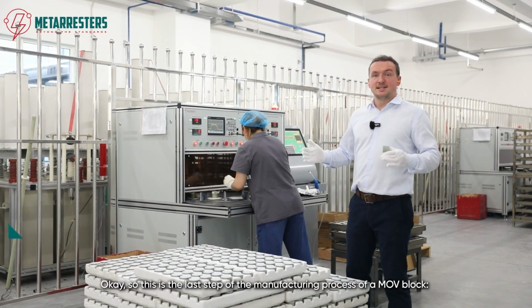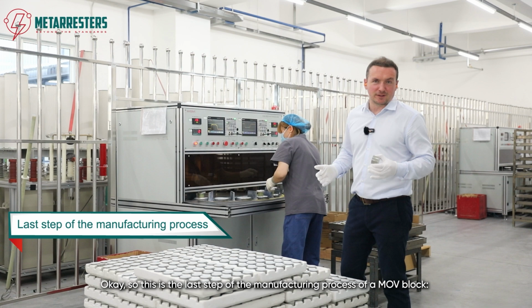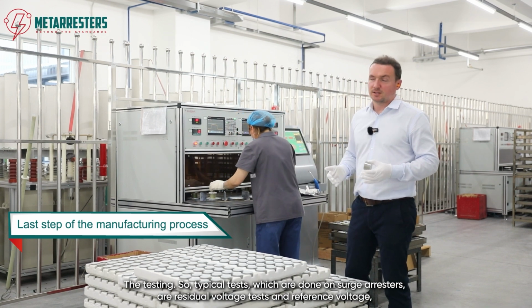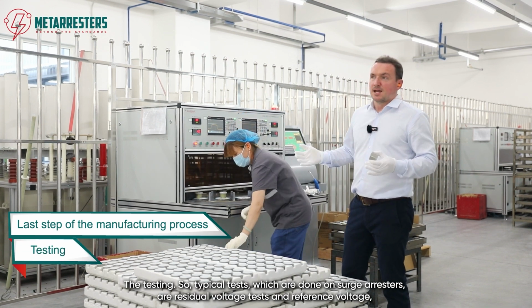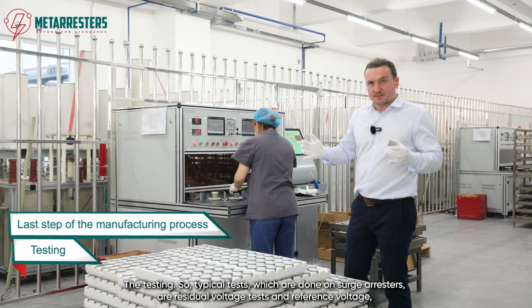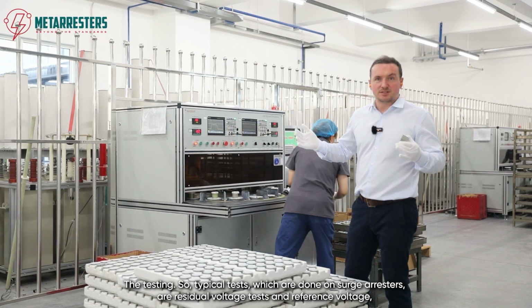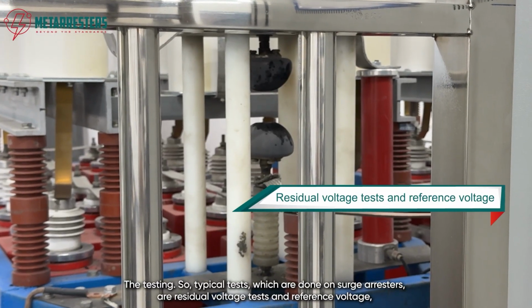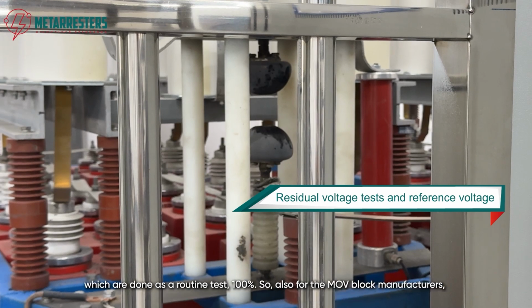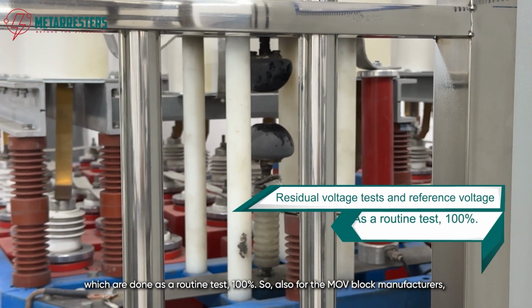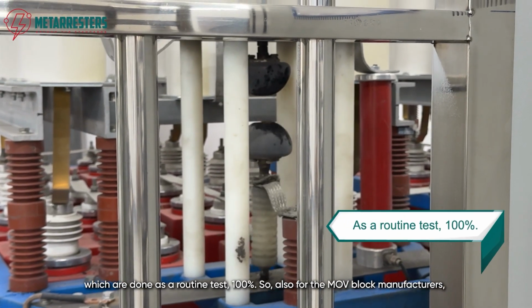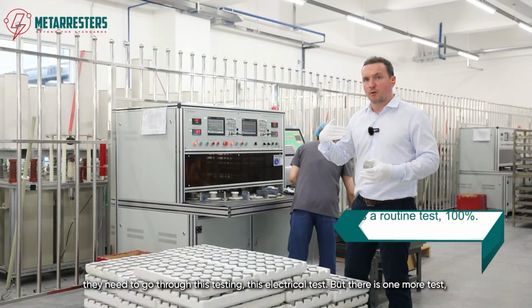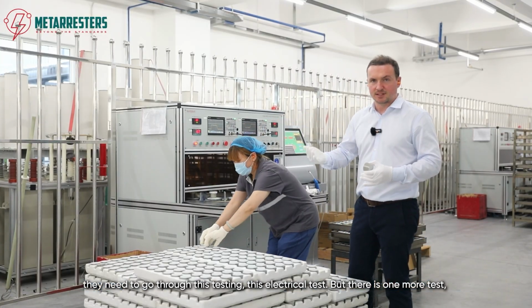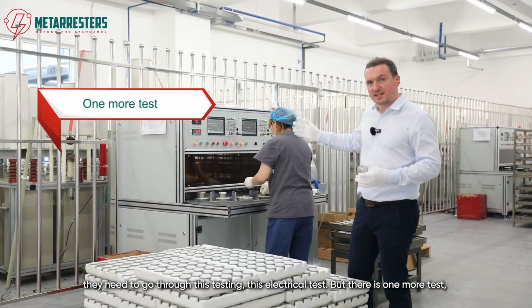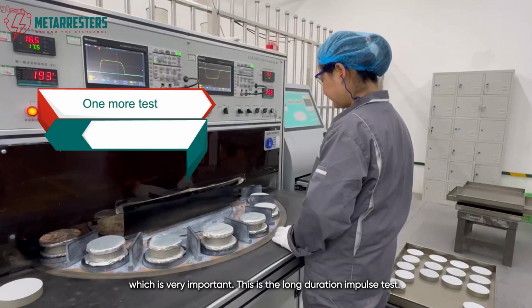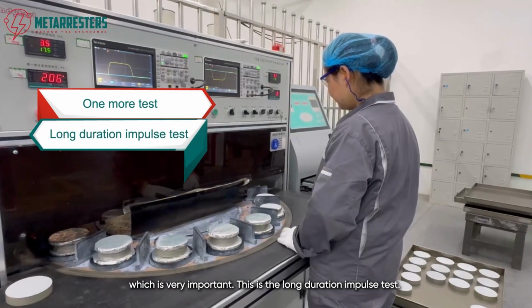Okay, so this is the last step of the manufacturing process of a MOV block, the testing. Typical tests which are done on surge arresters are the residual voltage tests and reference voltage, which are done as a routine test, 100%. So also for the MOV block manufacturers, they need to go through this electrical test. But there is one more test which is very important. This is the long duration impulse test.